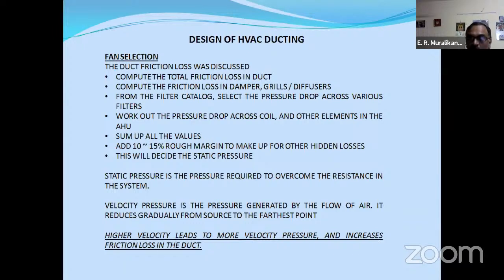So here, if your duct aspect ratio is not properly done, suppose you're having a very thin, narrow duct with high velocity, initially the velocity pressure will be high at the first grill, and at the last grill there will be very low velocity. The velocity pressure is very much essential to define the air path with proper distribution. Otherwise, what will happen is some places you will have a good amount of air, some places you will not. So this is a very important thing. People have to pay more attention to the calculations rather than going on assumptions and some thumb rules.